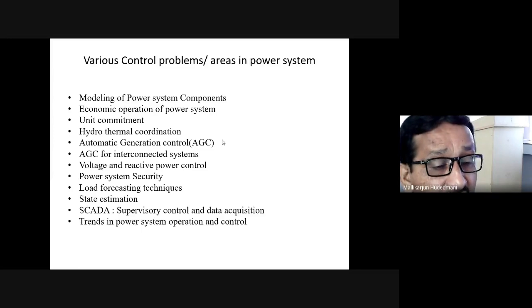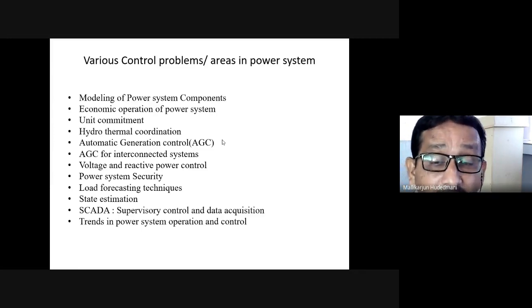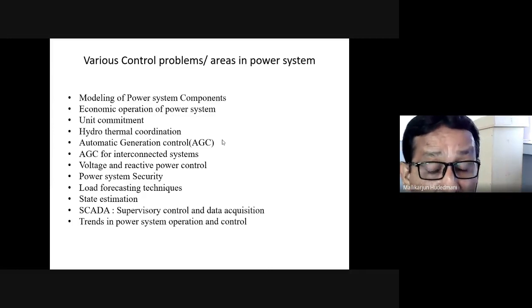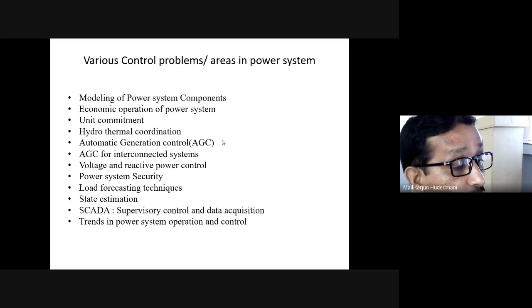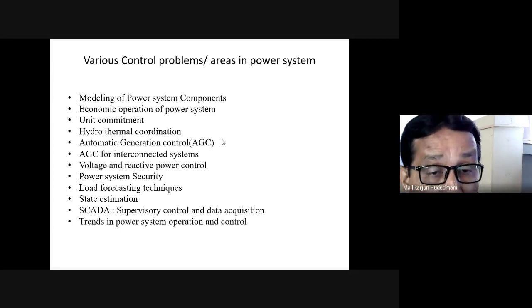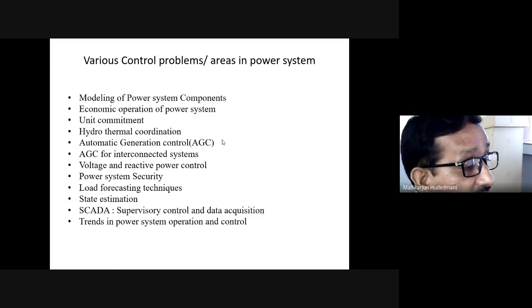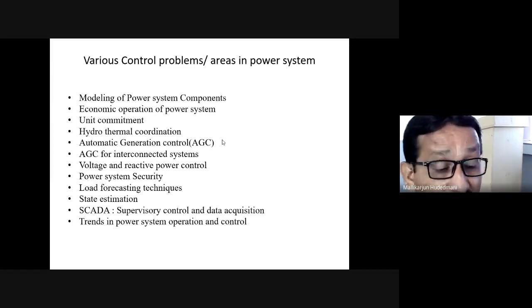As the load changes, it is natural to see a dip in the frequency. How that dip in frequency is controlled automatically, by managing the input fuel to the turbine, together with the two separate control loops, is done under the heading automatic generation control.